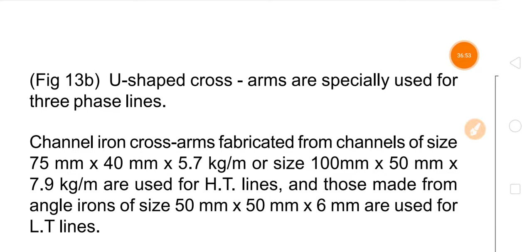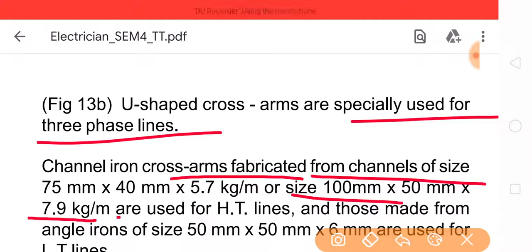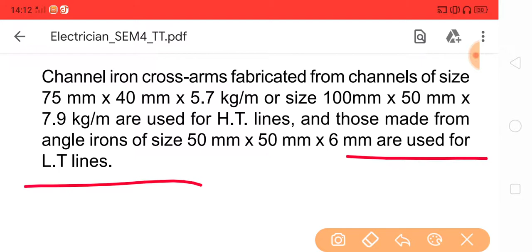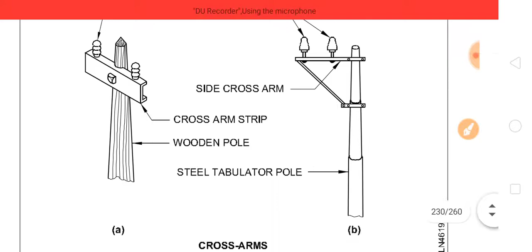Channel iron cross arms are fabricated from channels of size 75 by 40 mm by 5.7 kg per meter, and a size of 100 by 50 mm by 7.9 kg per meter, used for HT lines, and those made from angle irons of size 50 by 50 mm by 6 mm are used for LT lines. This is the shackle insulator and this is a pin insulator. Side cross arm strip, and this is wooden poles and this is the steel tubular pole. Cross arm.